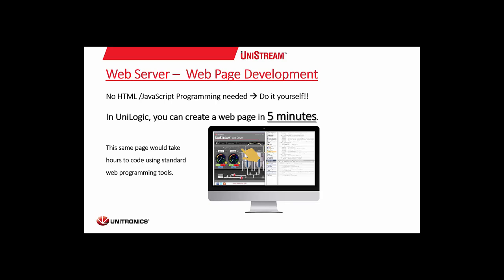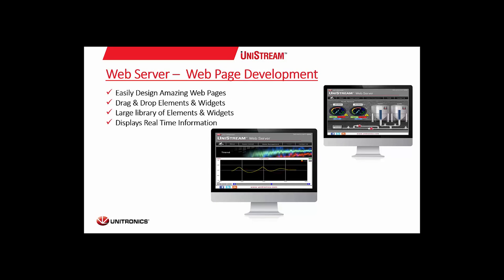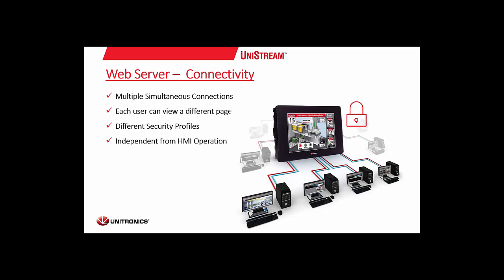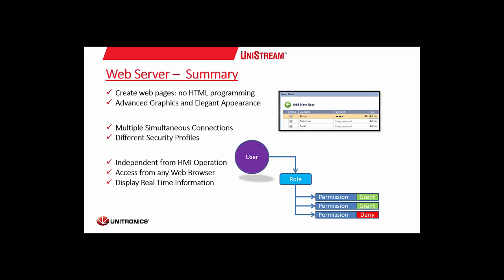While it does feature a more limited set of functionality than the HMI editor, the web page still offers the ability to view any sort of data and change most functionality of the PLC from it. It also gives you the additional option of having hyperlinks to go to certain web pages that you may want to. It also allows for multiple users to connect to the PLC at the same time from wherever they may be. As long as it's set up in your network, they'd even be able to access the PLC from outside of your local area. Again, web page is super easy. Anyone can do it, and it's exactly the same as making an HMI on your PLC.